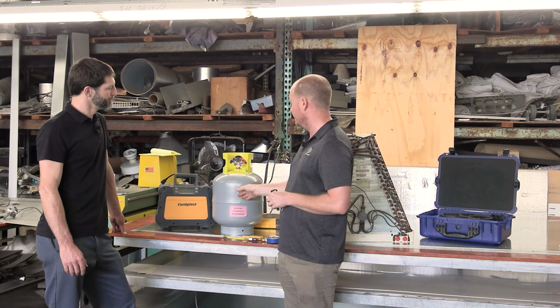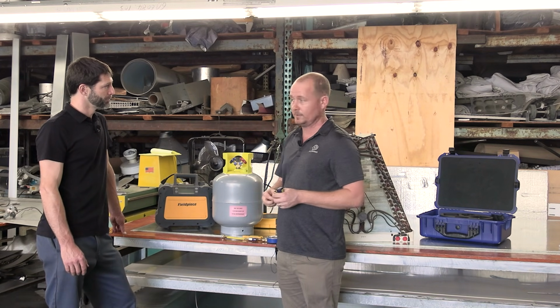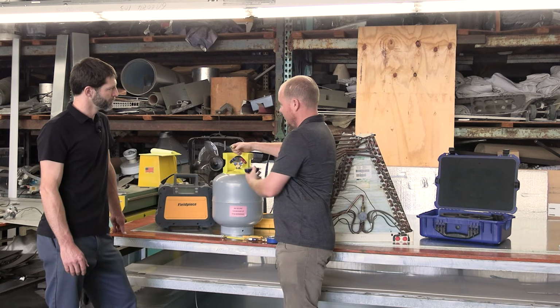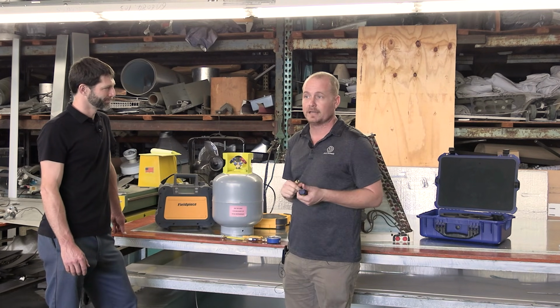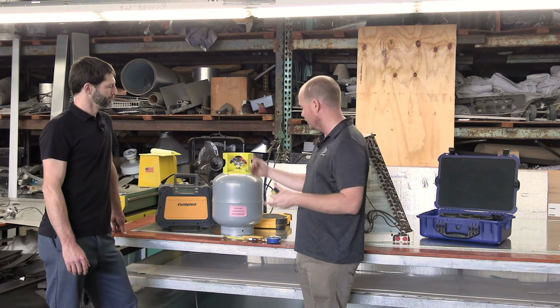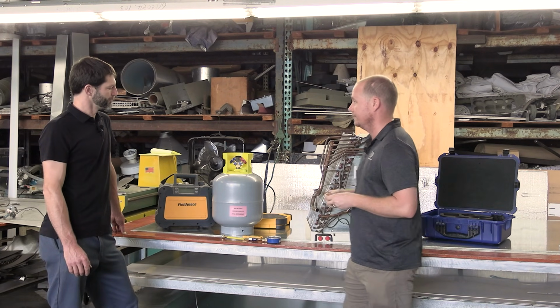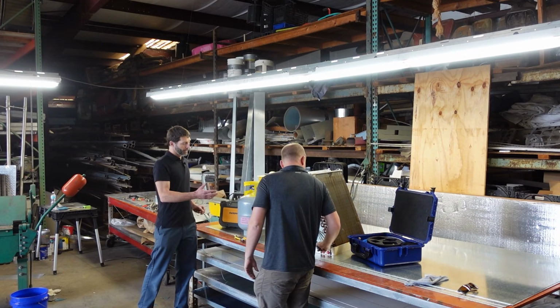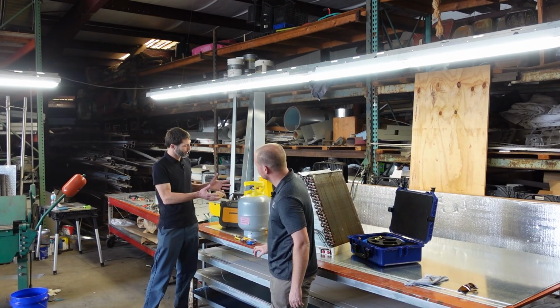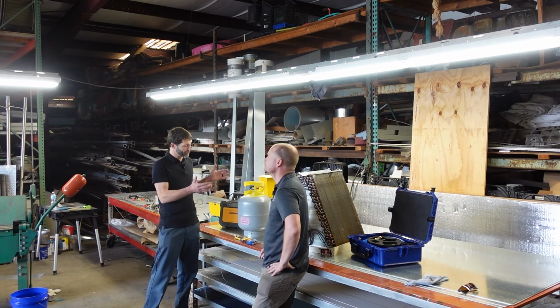So there's less restriction on the vapor side than there is on the liquid side. So you can hook your micron gauge on the liquid side, connect there, pull a deep vacuum on it, get it below 500 microns, and then you're ready to go ahead and put refrigerant into the tank. Yeah, and I would advise you to do that right before you're going to be recovering refrigerant into that tank.